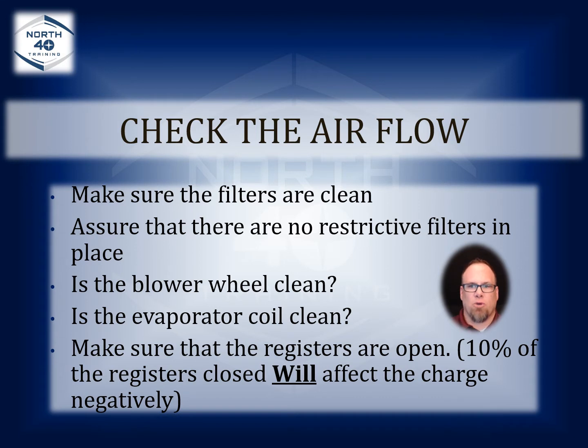Are the registers open? Now think about that. If you're only closing 10%, the average home has somewhere around 25 to 30 registers. That's 3 registers in a home that are closed. Probably most of the homes that you go in will have registers closed in them. It doesn't take much to create a negative effect in closing those registers.